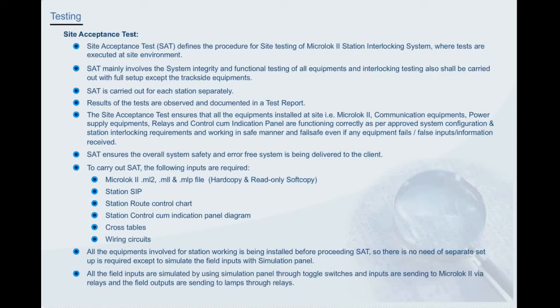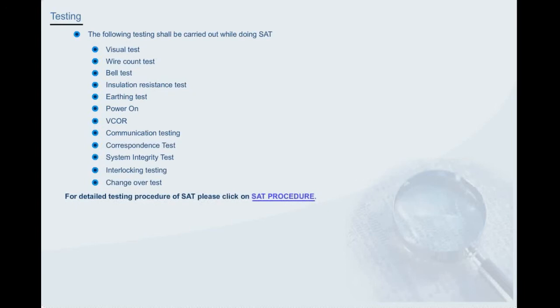All the field inputs are simulated by using simulation panel through toggle switches, and inputs are sent to Microlock 2 via relays, and the field outputs are sent to lamps through relays. The following testing shall be carried out while doing site acceptance test: visual test, wire count test, bell test, insulation resistance test, earthing test, power on, vital cutoff relay, communication testing, correspondence test, system integrity test, interlocking testing, changeover test. For detailed testing procedure of site acceptance test, please click on SAT Procedure.